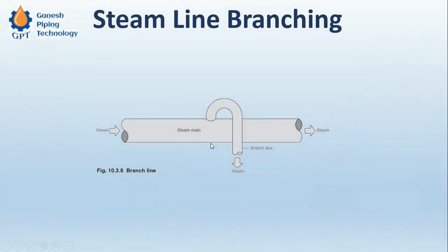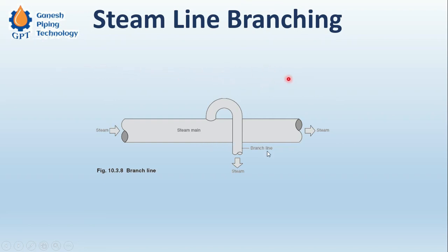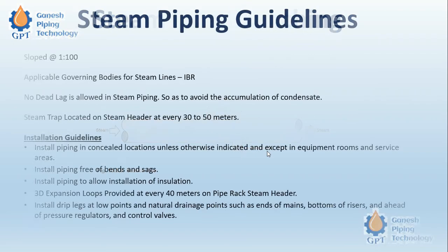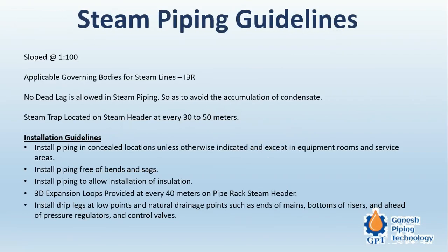Branching is taken from the top for steam because steam being a gas, we get a pure quantity of steam without traces of condensate. Since condensate settles at the bottom, taking the branch from the top ensures clean steam. This is an important guideline to consider when designing or installing steam piping.